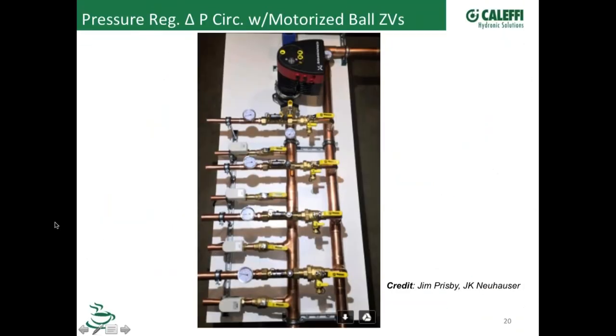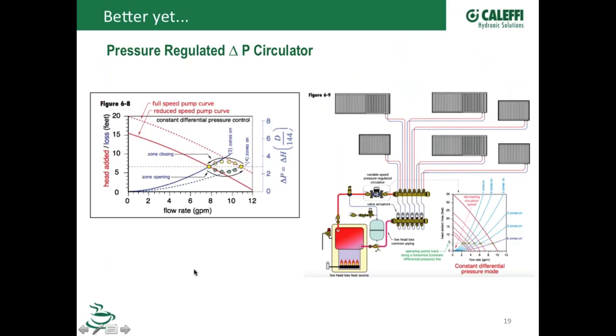Yeah, here's Bob. Yeah, go ahead. Oh, I was just going to mention too, we got a question from Frank, one of the pre-submitted questions. He was curious about the proper pressure settings for ECM variable speed circulators when zone valves are used. I think you could probably add to this, but it kind of goes back to the planning that you talked about before and figuring out what your head loss is through all these parallel circuits, and then obviously you're going to need to set your circulator to that pressure setting for whatever maximum head loss is going to be based on what your flow requirements are.